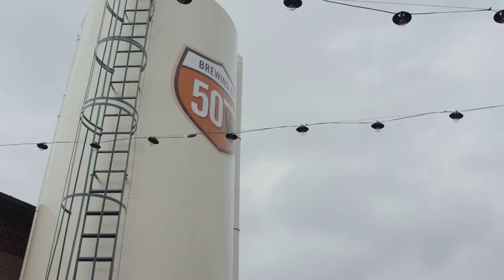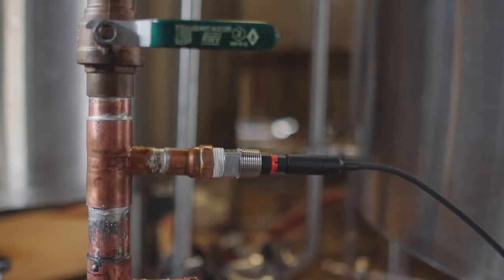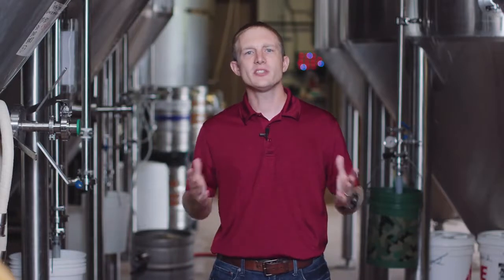Hello, we're here today at 50 West Brewery in Cincinnati, Ohio, where I'm going to walk you through setup and configuration of their Knick Stratos Evo transmitter. This MemoSense pH loop will be measuring and controlling the acid dosing of the incoming water. This ensures the water is within specification prior to the start of the brewing process.